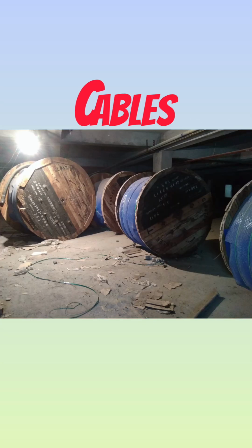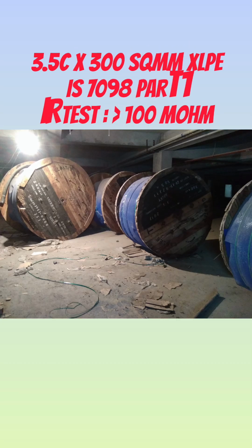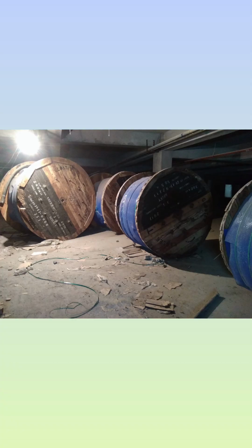For cables, we received 3.5 core 300 square XLPE cables. As per IS 1255, a pre-installation insulation resistance test was conducted. The acceptance criteria for LT cable is a minimum of 100 megaohm. All drums were stored on raised hard stands under cover storage.